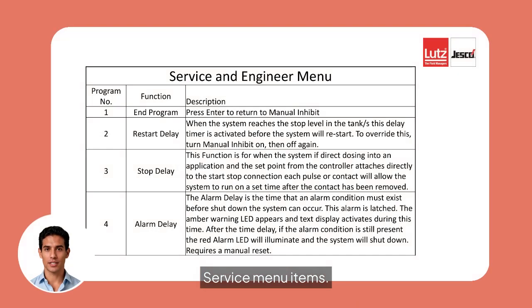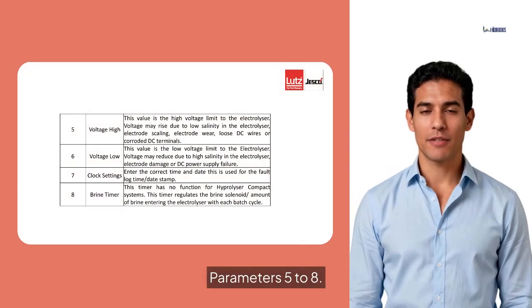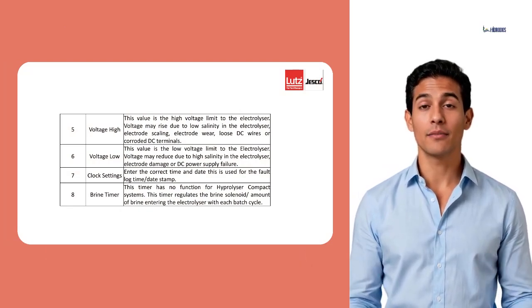Service menu items 1 to 4 manage basic timing. End program exits to manual inhibit. Restart delay defines how long the system waits before restarting after reaching tank stop level. Stop delay supports direct dosing applications, and alarm delay sets how long an alarm may persist before shutdown. Parameters 5 to 8 protect the electrolyzer and support logging.